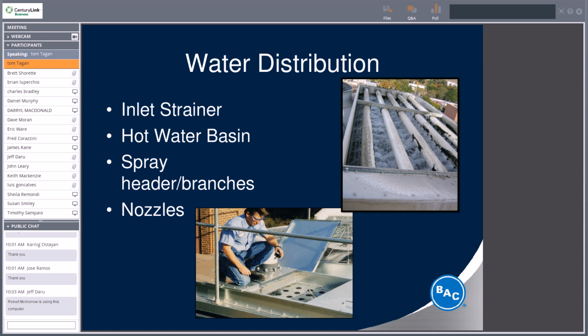And again, the tower is going to operate more efficiently and prevent scale buildup if you have even water distribution over the entire fill. Scale buildup or any biofilms tend to develop when you get into a wet dry situation. Also, if you have uneven water flows during the winter, that's when you can get some ice. You know, if you've got water simply trickling out of one because of a plugged nozzle, there's more opportunity to develop ice there than there would be if you had nice, even, full flow.